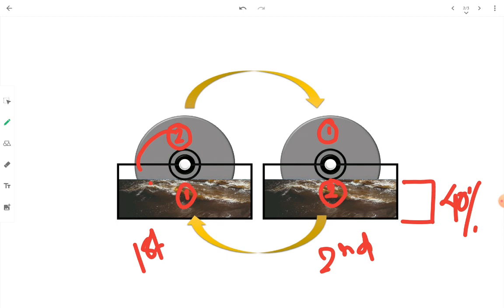When point 1 is exposed to air, the bacteria receive oxygen for their decomposition processes. Then in the next cycle, the same surface area submerges in the wastewater. Therefore, a continuous cycle of submergence where organic matter attaches to the disc and then exposure to air ensures the two essential parameters—food and oxygen—are continuously made available for the bacteria.